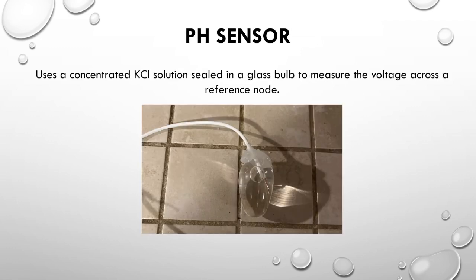Finally, the pH sensor uses a concentrated KCl solution sealed in a glass bulb to measure voltage across a reference node. It's a bad picture, so you can't really see the reference node on the other side of the bulb, or the hot glue. It uses the concentrated KCl solution to check resistance, but really it's measuring the voltage across the reference node and the node inside the bulb.